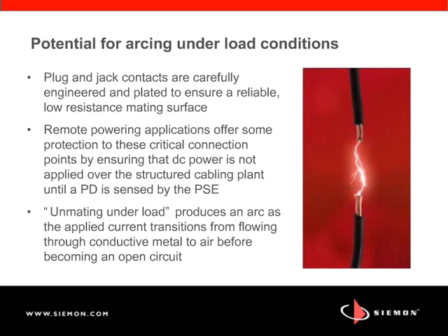Unfortunately, unless the power device is shut off beforehand, the power sourcing equipment doesn't know to discontinue power delivery if the modular plug-jack connection is disengaged. This condition is commonly referred to as unmating under load, and it does produce an arc as the applied current transitions from flowing through conductive metal to flowing through air before becoming an open circuit.